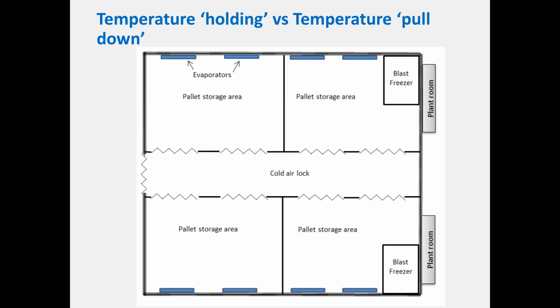So the difference between the two is that the freezer or the chiller, the unit designed for pull down, will have relatively high cooling capacity per unit volume, whereas the storage area is going to have a much larger volume and not as much refrigeration capacity per unit volume. And it's important to recognize that you don't want to overload a cool store or a cold store. It's not really designed for pull down. So if you fill it full of warm product, it's going to struggle.